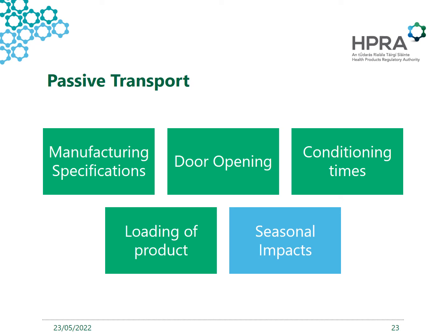We then need to think of the effect of the following. One is the loading of the product. Loading a high number of ambient bags into a fridge or freezer will of course cause a temperature spike. The same goes for exposing the storage area to ambient temperatures by means of door openings. Whether this is done in one large go, with all products going in at once, or by adding smaller portions of ambient bags with multiple shorter door openings, all of the above will have an impact on the core temperature of the fridge or freezer. Consideration should be given to this when conditioning the packs during the validation study and during normal operating conditions.